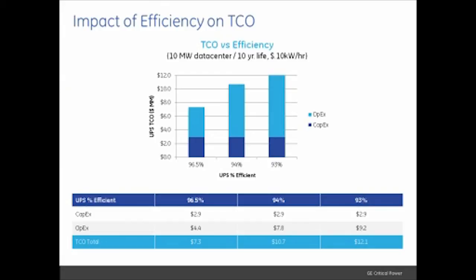For UPSs, most TCOs are either a 10-year or 15-year life cycle, and that has to do with lining up with battery replacement cycle, availability of parts after a 15-year period, availability of technicians familiar with that particular model, etc. But on this chart, 10 years, 10 cents a kilowatt hour, a 10 megawatt data center, we're assuming the UPSs are loaded 50%, so it would be a system plus system design. And the OPEX is much greater than the CAPEX in each case.